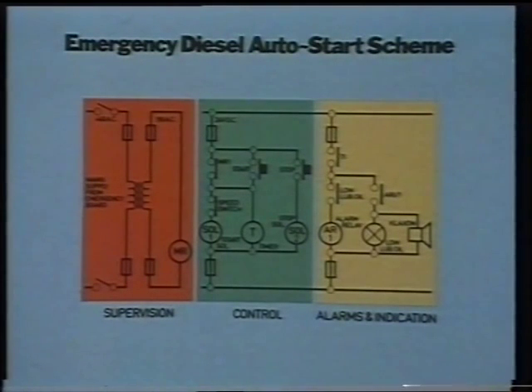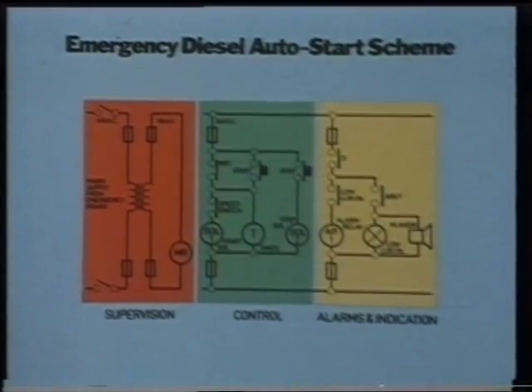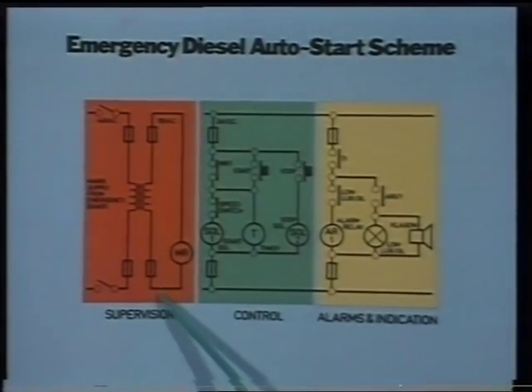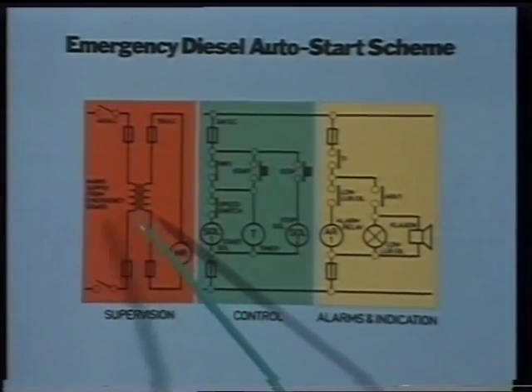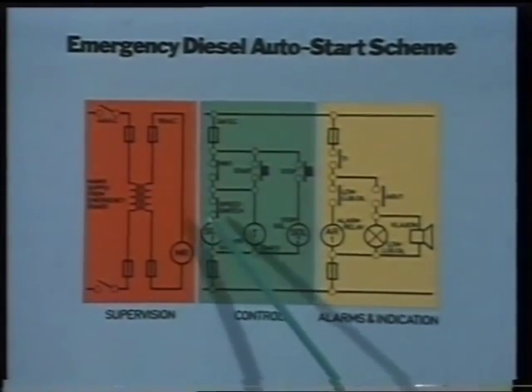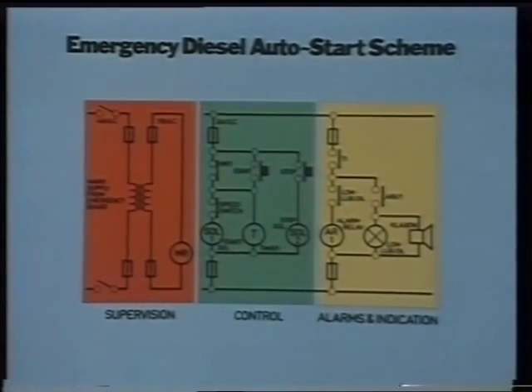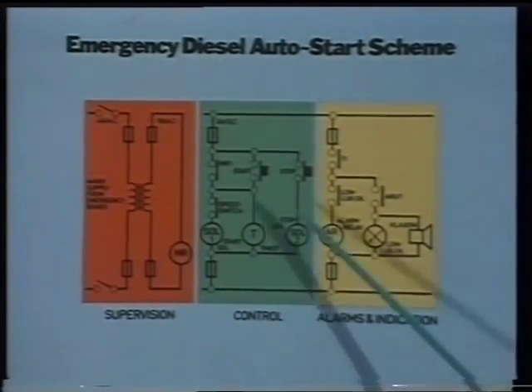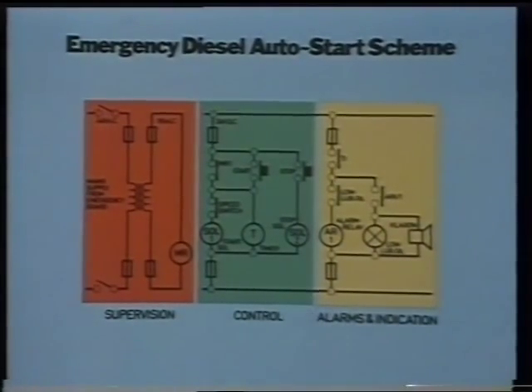This drawing shows the circuit arrangement for a typical emergency AC generator starter panel. The supervision circuit senses the loss of the main electrical supply. The sensing relay initiates automatic run-up of the emergency diesel via the control circuit supplied from the emergency batteries. Alarms and indications for high temperature, low lube oil and loss of coolant are also powered from the emergency supply. A similar system is used for auto-starting the standby diesel alternator.